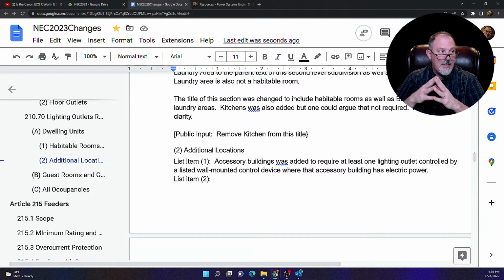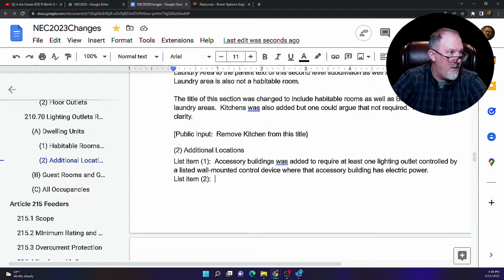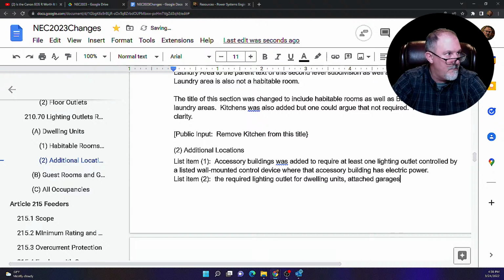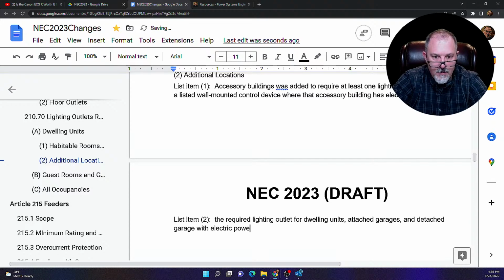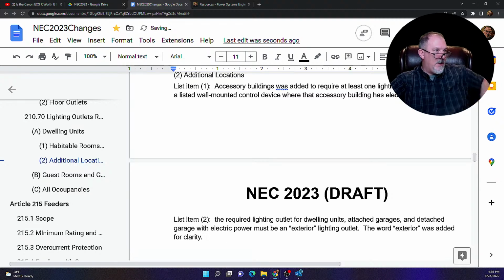It says for dwelling units, attached garages, and detached garages with electric power, at least one exterior lighting outlet. So the required lighting outlet for dwelling units, attached garages, and detached garages with electric power must be an exterior lighting outlet. The word exterior was added for clarity. I'm going to read our panel statement on this one.